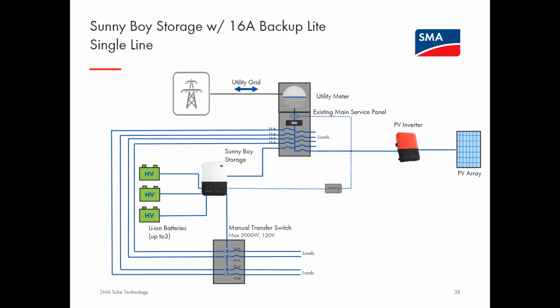And then lastly, here's a line diagram showing what that Backup Lite installation would look like. In this case, we select up to four 15 amp circuits inside of the home and pass them through a manual transfer switch. The manual transfer switch is connected to the output of the secure power supply within the SunnyBoy Storage. Again, that's capable of delivering up to 2,000 watts at 120 volts, so 16 amps maximum.